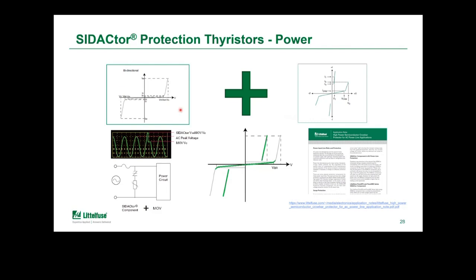If we look at the curves of the MOV and the SIDACtor, we have a clamping device and a crowbar device. By adding the SIDACtor in series, the standoff voltage is a combination of the two, so we can again reduce the voltage rating of the MOV, and we end up with a curve that looks a little more like this. We still have a foldback feature: once the SIDACtor reaches its breakdown or switching voltage, it drops down to essentially the clamping voltage of the MOV. So we can reduce the overall let-through energy within the MOV. There is an application note on our website that goes into more detail about how this works.